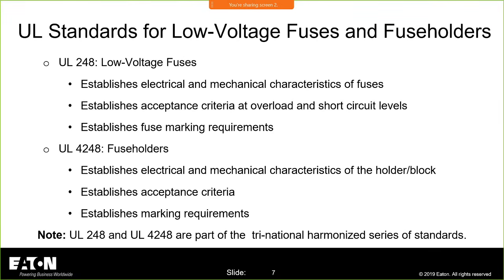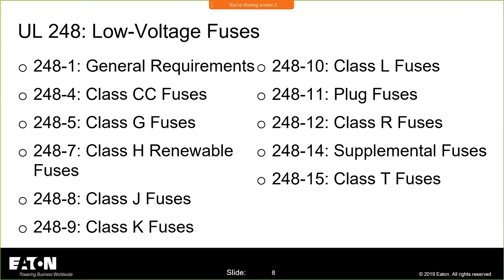Alrighty then. The UL standards that we use: UL 248, low voltage fuses. There are like 15 different parts to that standard. This establishes the performance criteria and all of the acceptance criteria for a fuse and a holder. 248 is the fuse, 4248 are the fuse holders. And they work hand in hand, because once we have a fuse class, that will define the dimensions of that fuse, and that tells us in 4248 the holders and how to make those and the dimensions. So they relate very closely with each other. But those are the two standards for the fuses themselves and the holders.